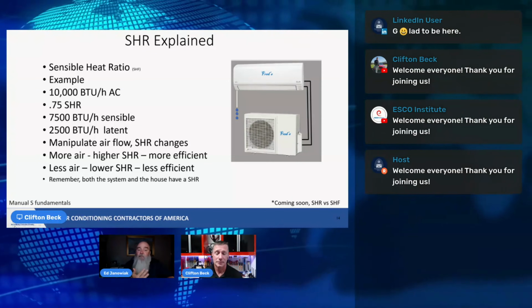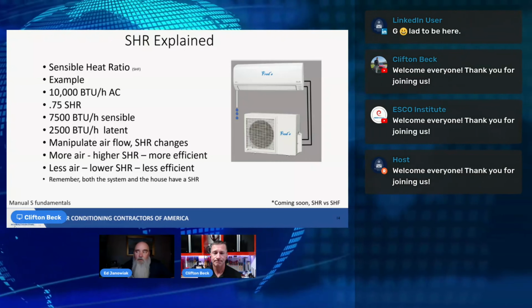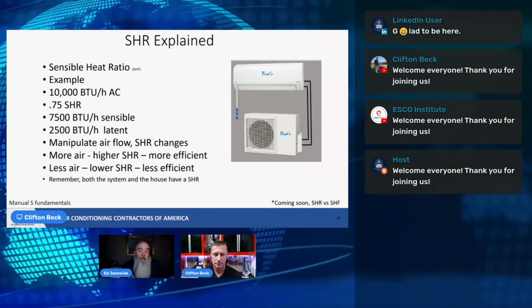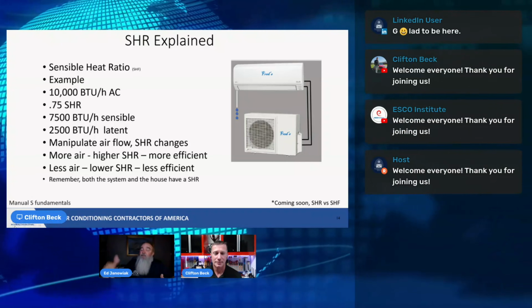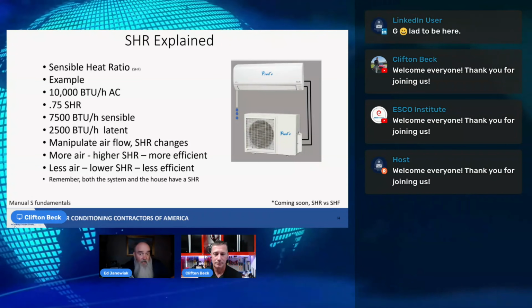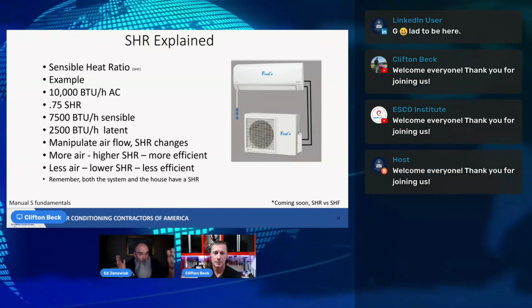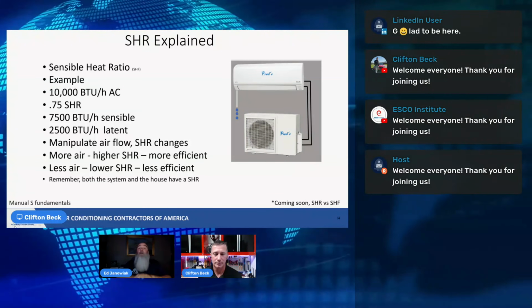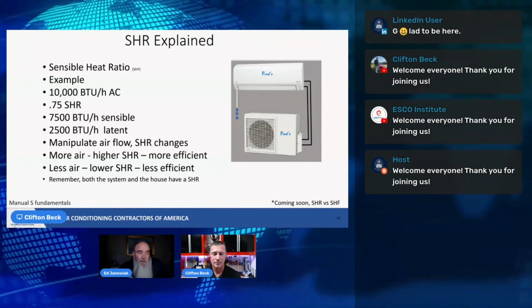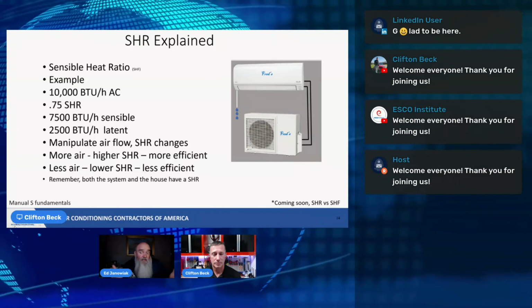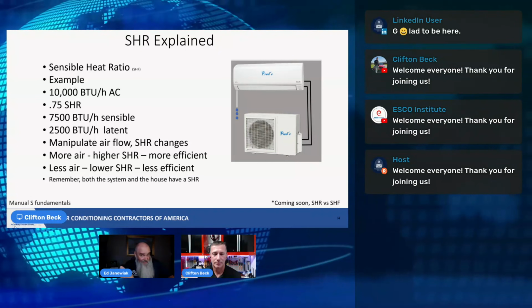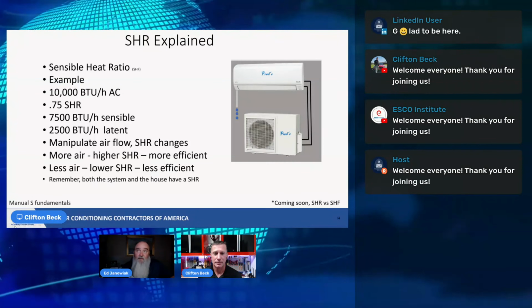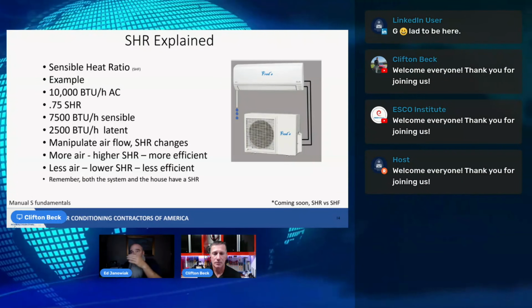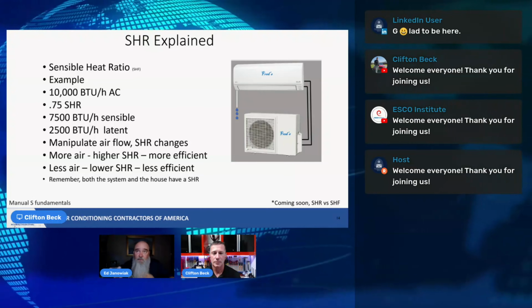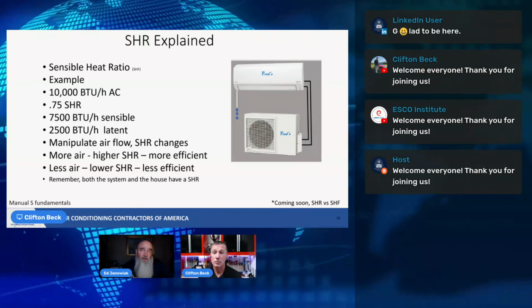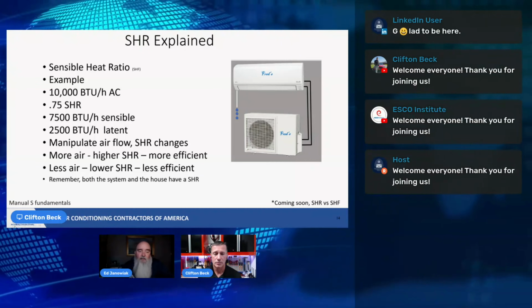You have somebody that's complaining their system is not able to control the temperature when it's really hot out. The definition of really hot out for me is above a design day. Well, increase their airflow. That might get you that couple of degrees that they're complaining about. Sure. The flip side, you have a house where the people are saying, I feel kind of sticky. Well, check that airflow. If it's higher than necessary, lower it, and it's going to dehumidify better. Correct. So under the 2,500 on the bullet points there, it says manipulate airflow and our sensible heat ratio changes. This is what the guidance in Manual S is all about.